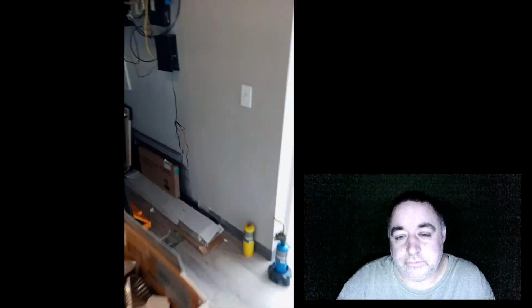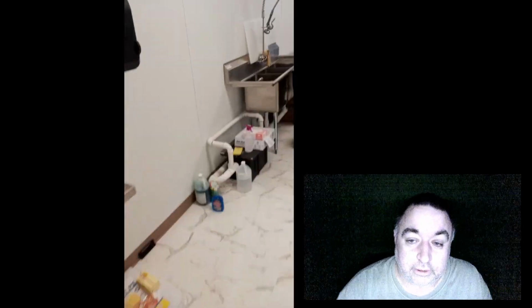I'm also not ready to stick it back in the wall yet, because I don't know if I have further problems. I have no idea why that breaker would have been loose like that, but I'm almost guaranteeing that's our problem. That may have caused the problem. Definitely could. You're making and breaking contact with the control board. It could definitely cause it to short out. It's only been in this location for a month. It was working fine until a couple of days ago. Transistors, capacitors, and diodes do all kinds of weird stuff.